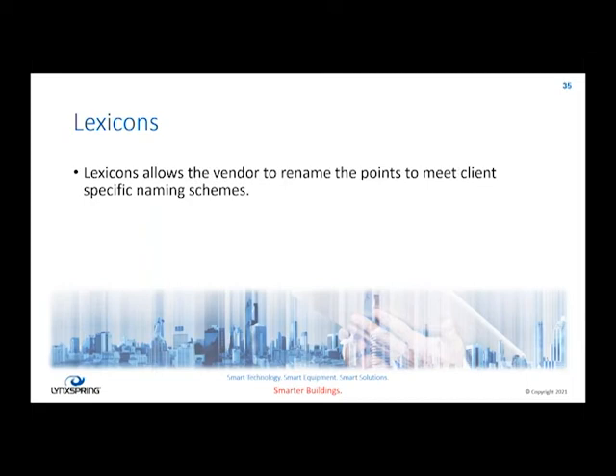Lexicons, we touched on this briefly. If you have 4 different major clients that all have their different naming conventions, you bring up your lexicon template, and I've called it discharge air temperature in the template. You can go back there and rename that DAT or DA temp. It doesn't matter. So after you install those lexicons, all of your histories, all of your alarms will come back with the naming convention that you picked. So even though we've called it discharge air temperature, the end user only sees DA temp.